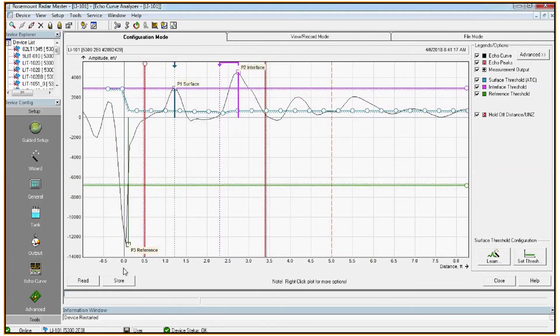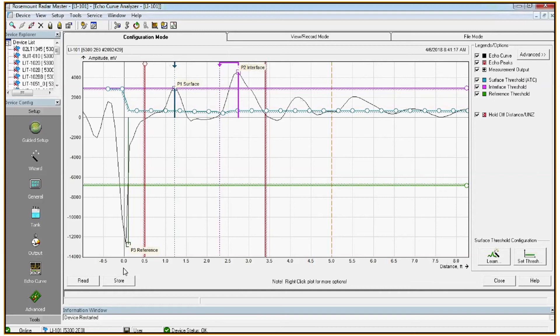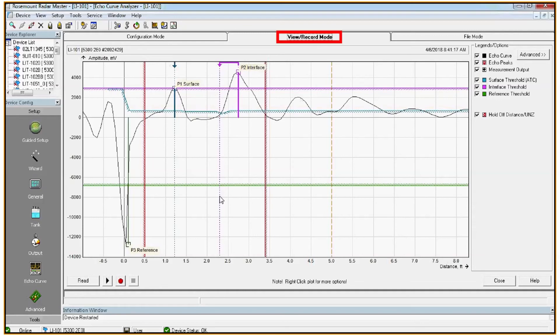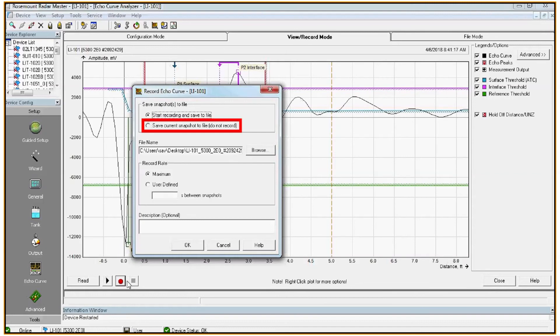Once the echo curve is loaded with product in the vessel, you should clearly see your P1 surface and interface peaks identified. If they are not tracking or things don't look quite right, you should save an echo curve so that you can send it in to us for support. Regardless, when we're done we should always save an as-left or with product echo curve. So again, the view record mode and click the little red circle in the bottom left corner to save. We'll select save current snapshot to file and click OK.